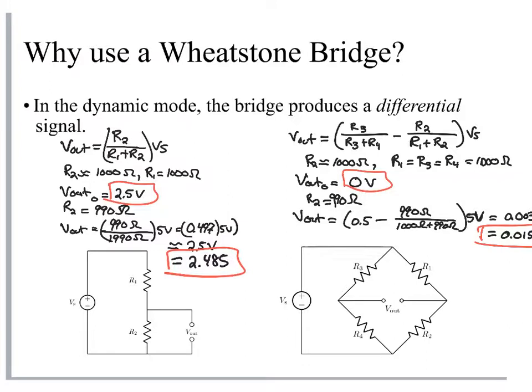On the other hand, we have our Wheatstone bridge where we've always got this reference being formed on the non-loaded side. And then we're comparing it with the sensor. As a result, we're forming the reference at the same time. We're doing this actually in hardware. We have a signal that is affected by the source voltage, but the reference is being taken into account. Our zero voltage reference is being taken into account at all times. And so therefore we're less prone to error.